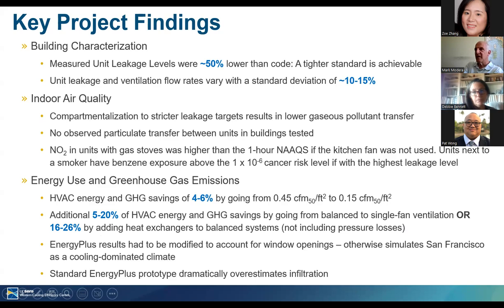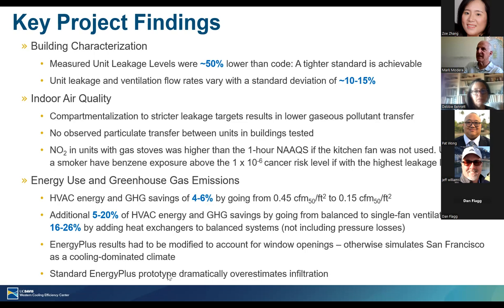Another takeaway was that the EnergyPlus results used for the baseline building had a rather high assumed infiltration rate. The other problem was that the way it's managed, it doesn't account for window openings. If you don't deal with that, it simulates San Francisco as a cooling-dominated climate, which is clearly not the case. The standard prototype dramatically overestimates infiltration based on our detailed modeling of infiltration rates.